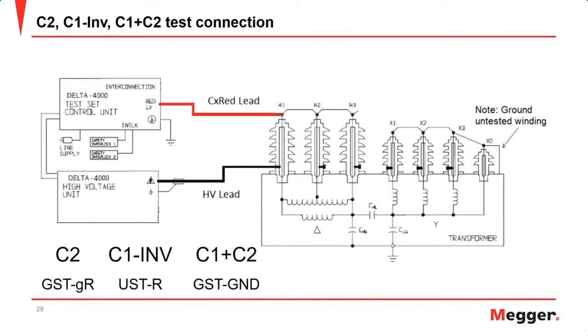One important note is that when you are doing the C2 tests, you will typically excite at either 500 or 2000 volts. It's going to be bushing by bushing which one you can use. If you're just going on safety and protecting the asset, then 500 volts is safe to use. When it comes to power factor, dissipation factor and capacitance, if you test at 500 volts or 2000 volts, you should not see a difference, especially for OIP bushings.